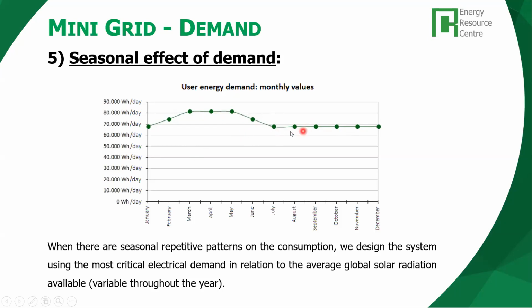It is different to choose the PV panels capacity to provide a power generation of 70 kilowatt hour per day or 80. This is 15% more or 15% less. 15% more of investment, of cost, or less. Okay, so it is important. And if we choose to size the PV generation capacity here, then what do we do with this deficit? We will need probably to have a genset and run this genset only for the additional demand need that will happen in a period of 2 or 3 months. Okay, that could be a solution.